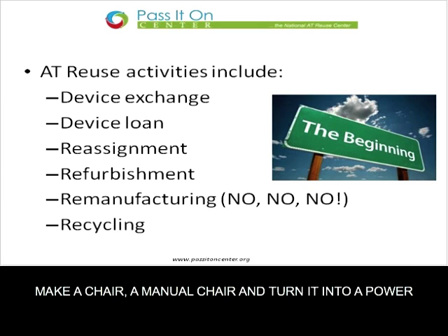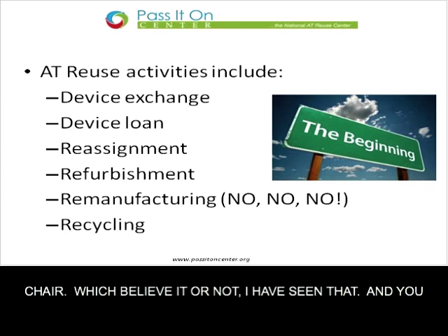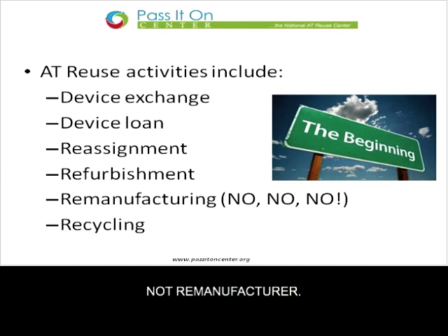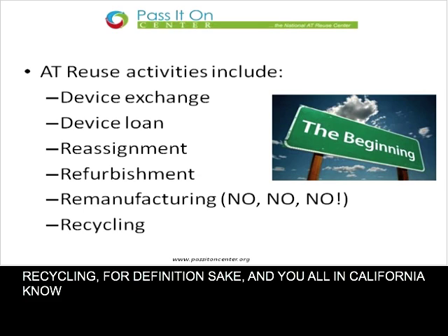If you remanufacture, you take, for example, an Invacare chair, and that's a manual chair, and you turn it into a power chair, which, believe it or not, I have seen, then you have created a new device, and that's not a good thing to do. So do not remanufacture. And on the slide here I say no, no, no.